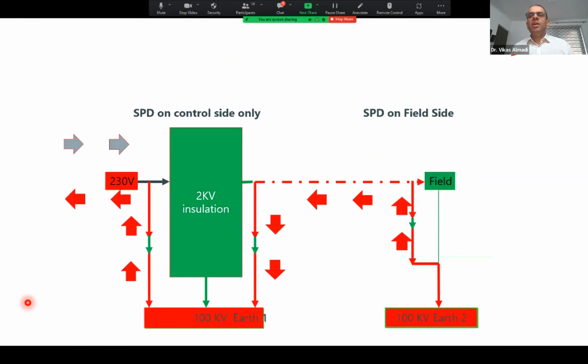But when we protect it via a bypass path like this, the current is not flowing through the main devices. In this case, current may be flowing still through the cables and through the earth and through the main transformer earth, but it will not flow through the equipment which are used for operation.